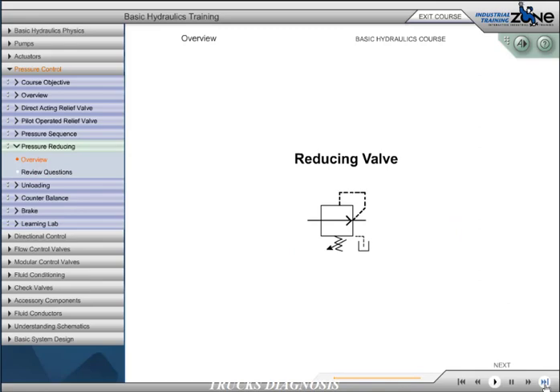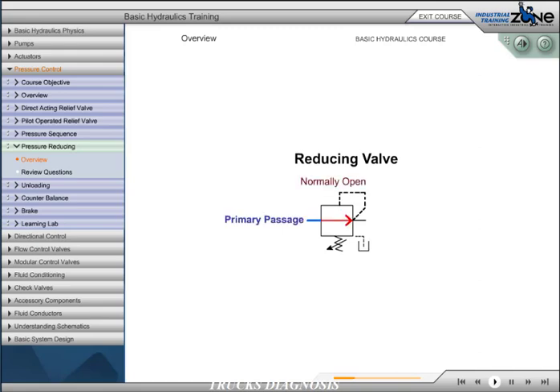A pressure reducing valve is a normally open pressure control valve used to limit pressure in one or more legs of a hydraulic circuit. Reduced pressure results in reduced force being generated. A pressure reducing valve is the only pressure control valve that is normally open. A normally open pressure control valve has primary and secondary passages connected. Pressure at the bottom of the spool is sensed from the pilot line, which is connected to the secondary port. Remember, a pressure reducing valve is normally open.